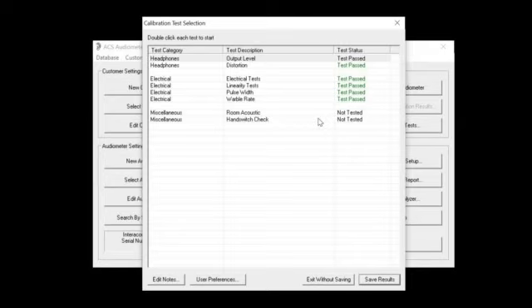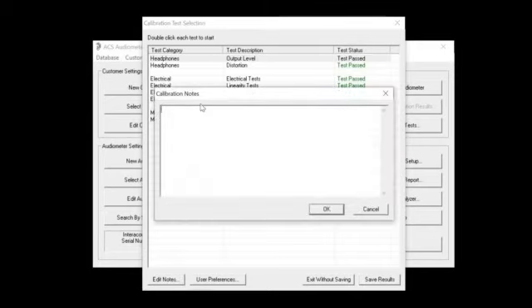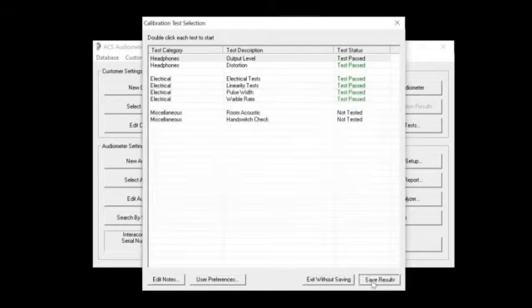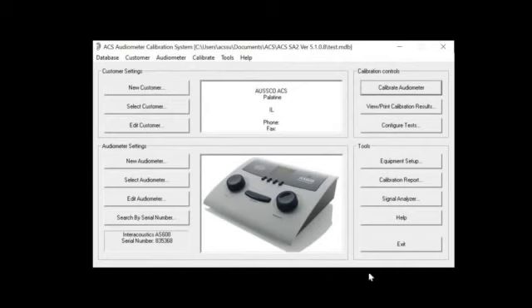On an industrial grade audiometer, it automatically comes up and forces you to check the hand switch. 99% of the time the audiometer is not working right, watch out, it's the hand switch. But I can edit the notes at this point. If I found out something that I want to talk about, I can come back in over here and add whatever kind of a little note that I want to pass on. This is part of the test procedure, and it's part of the certificate that's printed out. I'll just say OK. I'm going to save the results, and they're in the database.